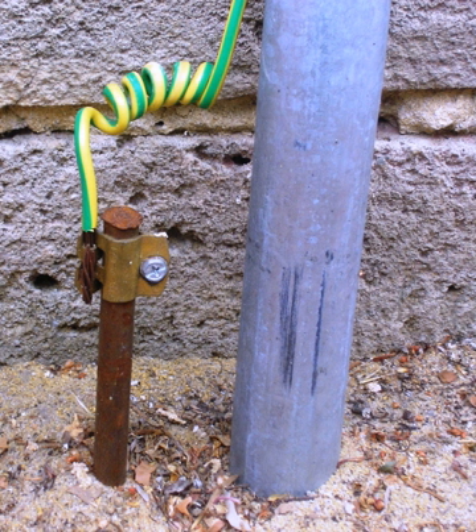Topic: Ungrounded systems. Where the danger of electric shock is high, special ungrounded power systems may be used to minimize possible leakage current to ground. Examples of such installations include patient care areas in hospitals, where medical equipment is directly connected to a patient and must not permit any power line current to pass into the patient's body. Medical systems include monitoring devices to warn of any increase of leakage current.